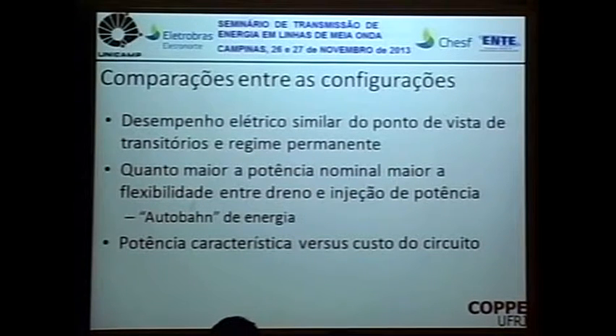The electrical performance was very similar. So there were differences in terms of values, but the overvoltages were always within the limits. The energization voltages were always within what was accepted, or even below 2 pu, because there's an unusual fact. These are very long lines, so the maneuver transients are damped. But if you consider the tower, the position of the surge arrestor, we would have a satisfactory performance as well.